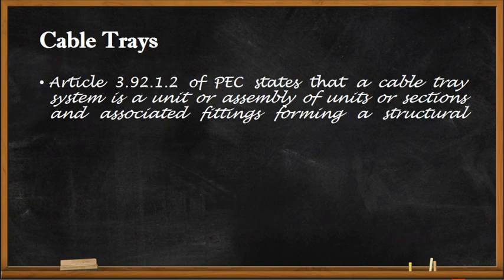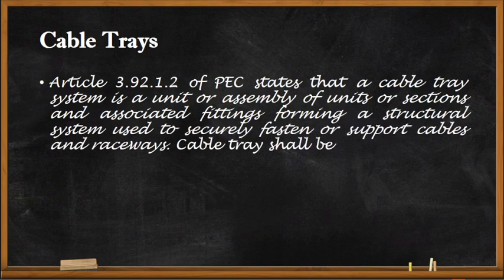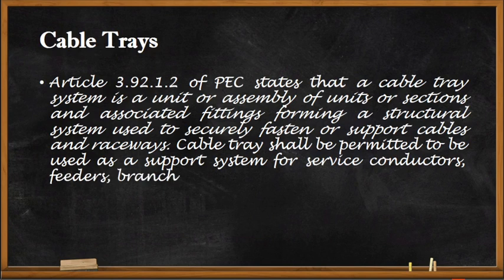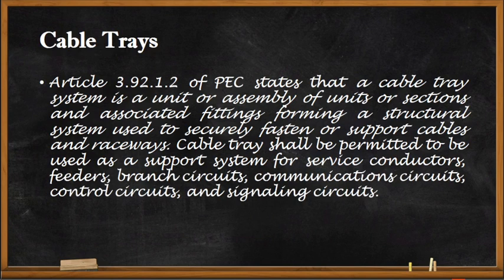Next is the cable tray. Article 3.92.1 of the Philippine Electrical Code states that a cable tray is a unit or assembly of units or sections and associated fittings forming a structural system used to securely fasten or support cables and raceways. Cable trays shall be permitted for use as support systems for service conductors, feeders, branch circuits, communication circuits, control circuits, and signaling circuits.